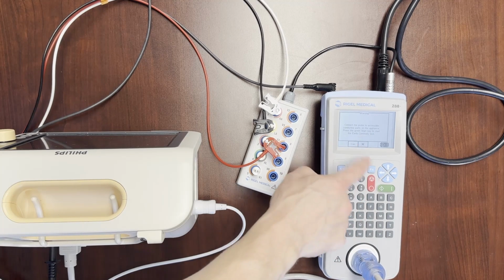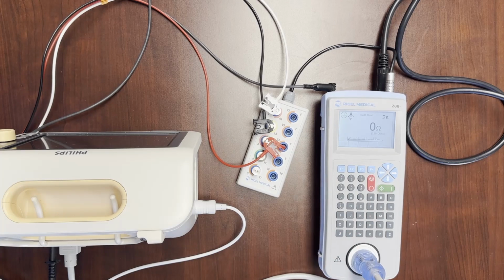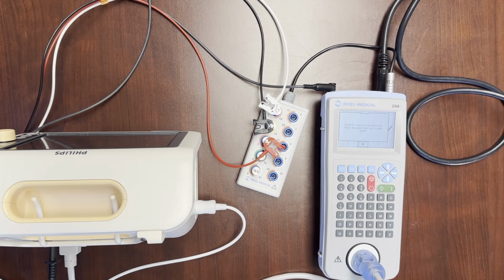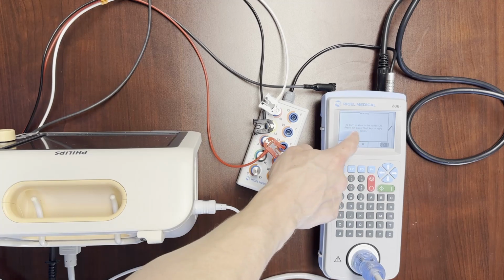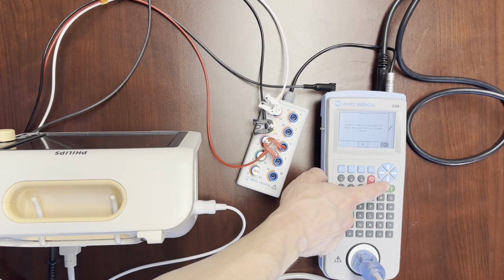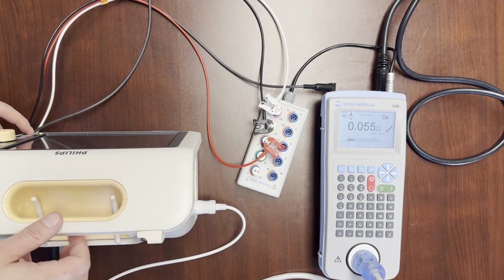See, applied parts are done. Literally it's running through this test fully automated. There's not much we have to do except just follow the prompts as the test runs. So you can see this is a lot easier than performing a test with a manual electrical safety analyzer. But at the end of the day, it's up to user preference.